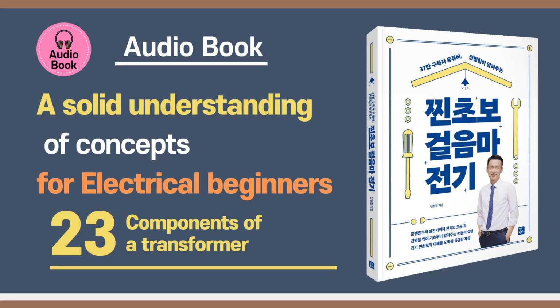With round wires, you always get those little gaps between them, right? Wasted space. But flat square wires can pack together much more tightly, almost like bricks, with less wasted space. This means you can fit more copper conductor material into the same area, which is great for big transformers carrying huge currents, more current capacity in the same size, basically. Reduces losses, too. It's a neat little optimization for big jobs. That makes perfect sense, getting the most conductor into the space available.